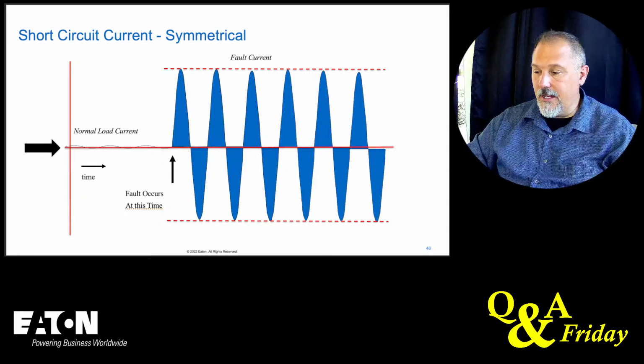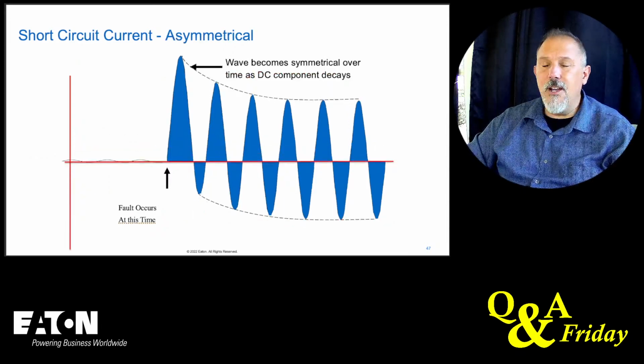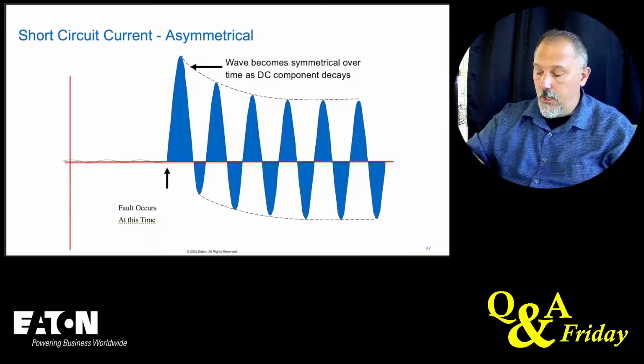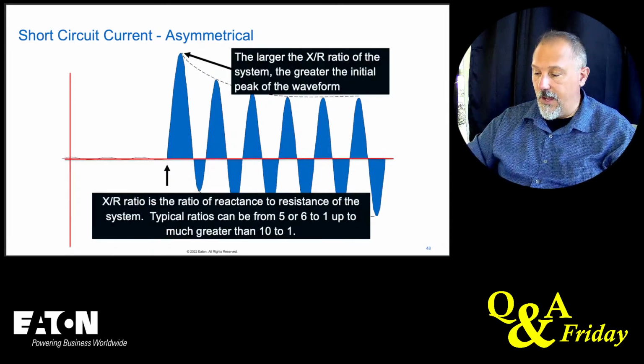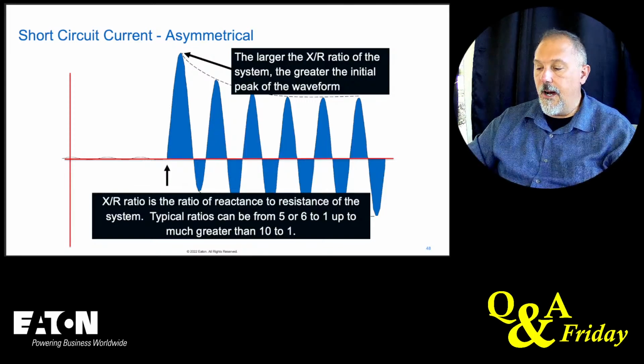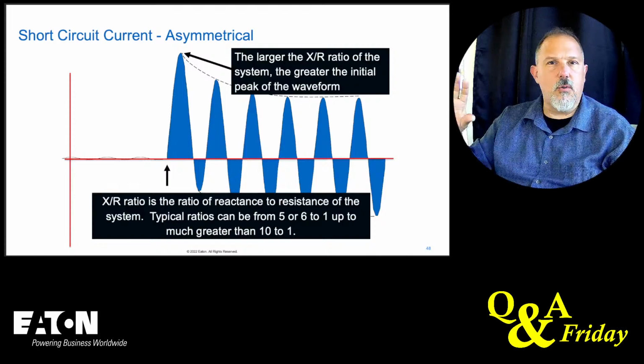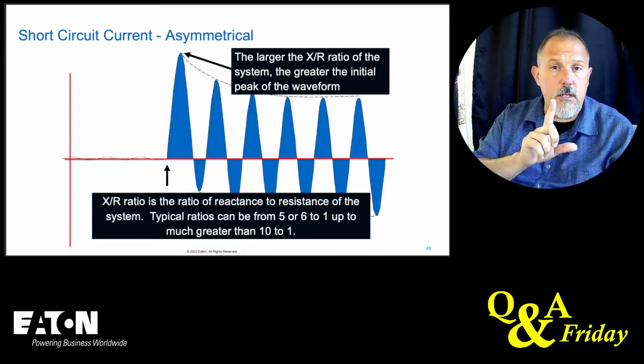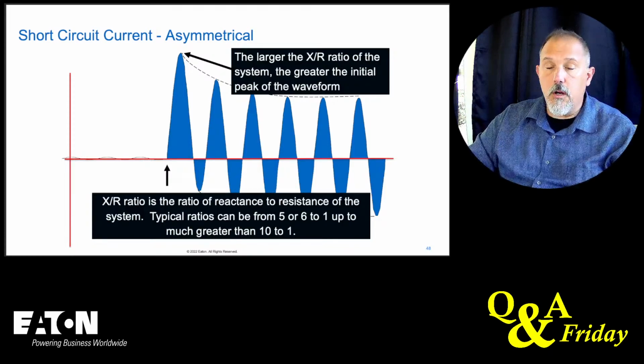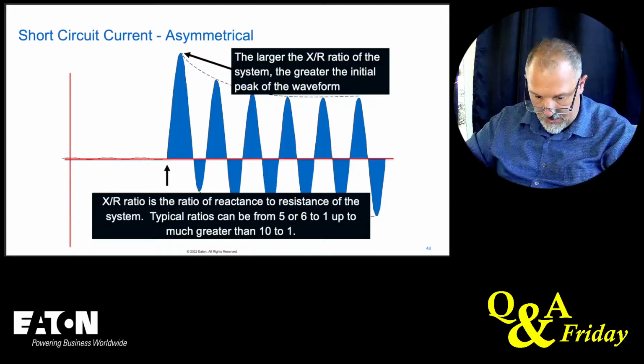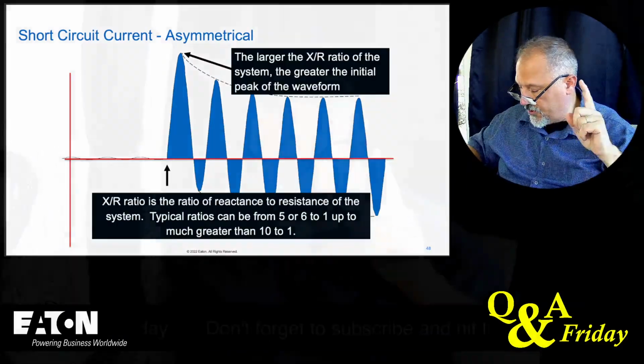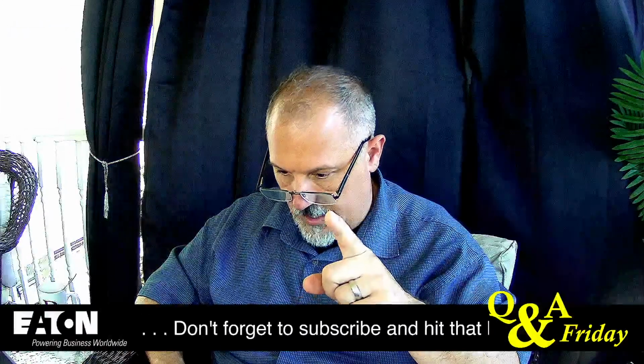And the reason I say that is because we pick an X to R value, which, again, your X to R ratios are typically from 5 or 6 to 1 up to 10 to 1. We pick what we think is the worst case scenario. And if you look at the literature for overcurrent protective devices from manufacturers, I'm going to show you one.